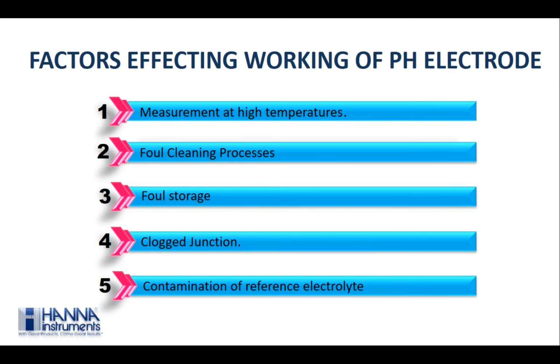Faulty storing practices also affect the working of the pH electrode. Storing the pH electrode in distilled water is the biggest misconception people have. Storing the pH electrode in distilled water will result in the leaching of glass, and also the leaching of salt from the reference electrolyte into the distilled water, as distilled water is a very aggressive solvent.